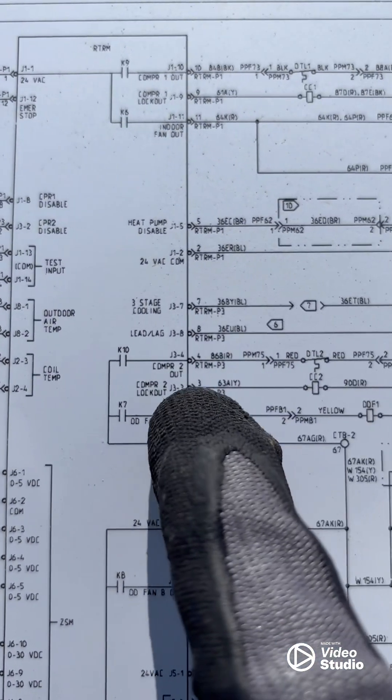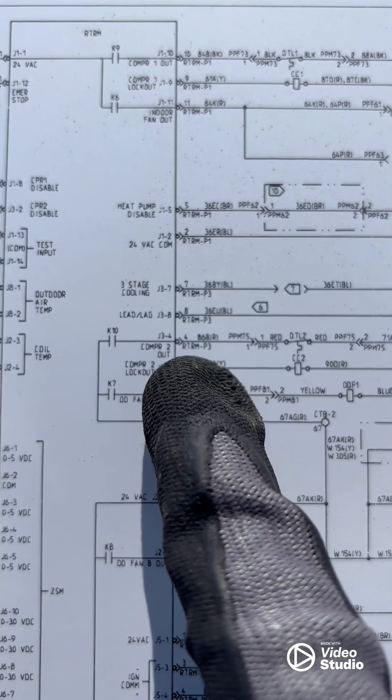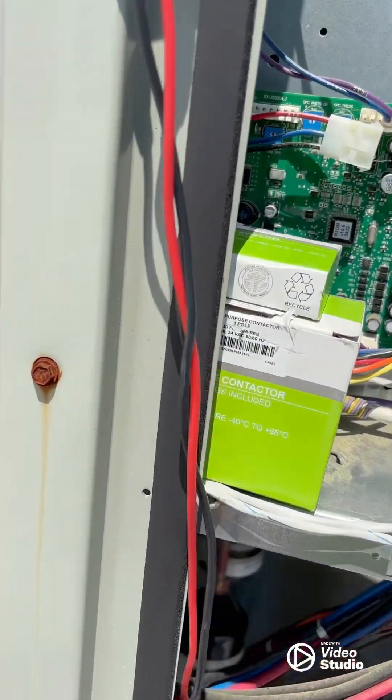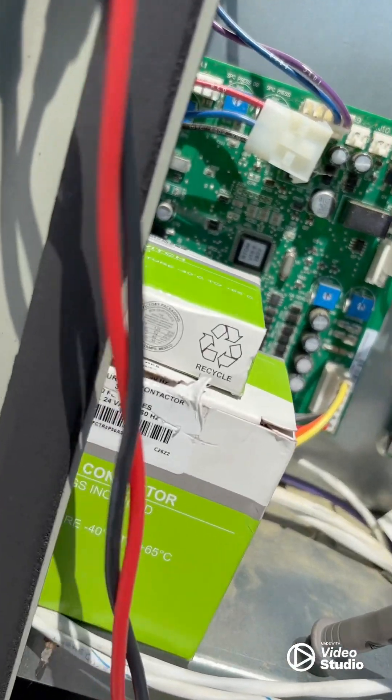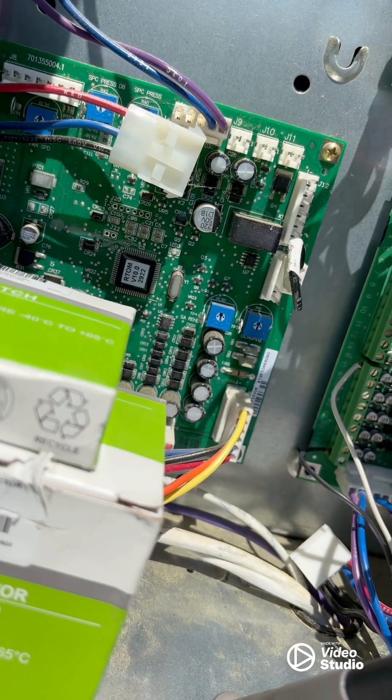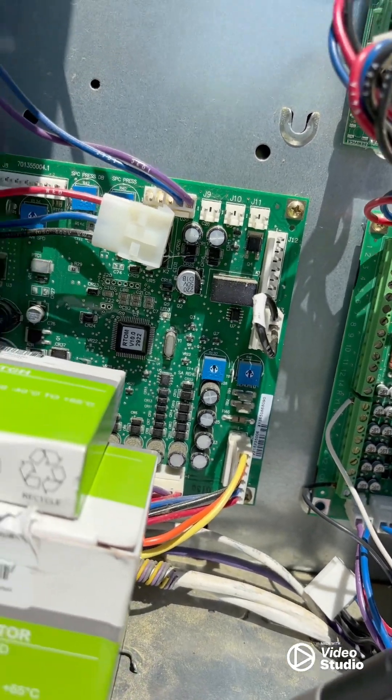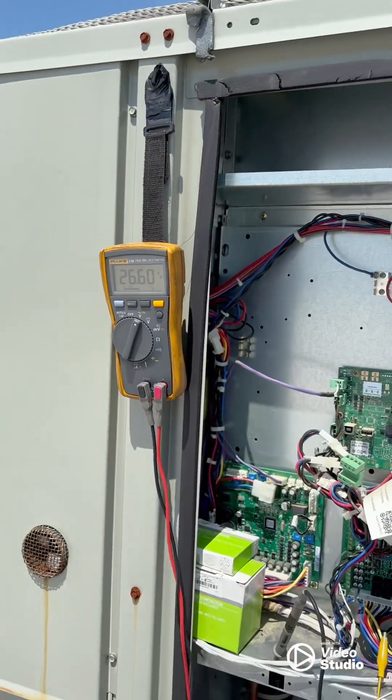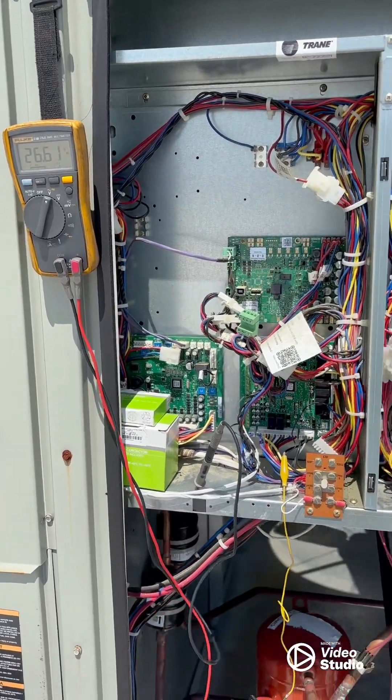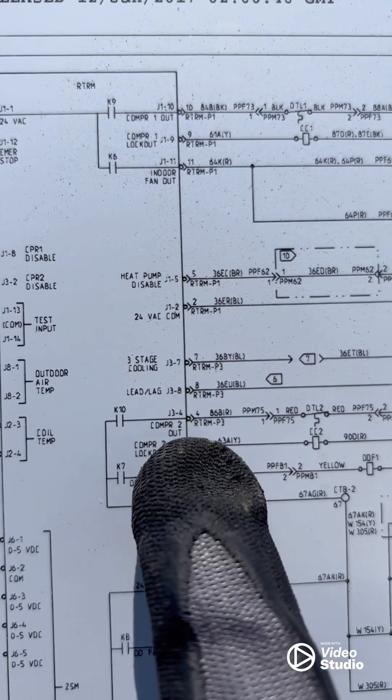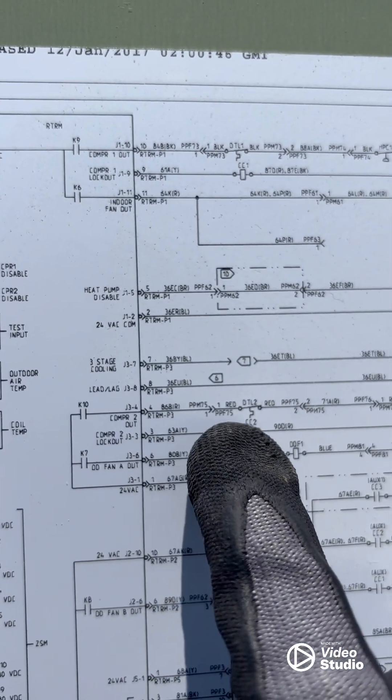It's actually supposed to be on J34, the red wire. We've got 26 volts coming out of J34. J34 is compressor 2 out.